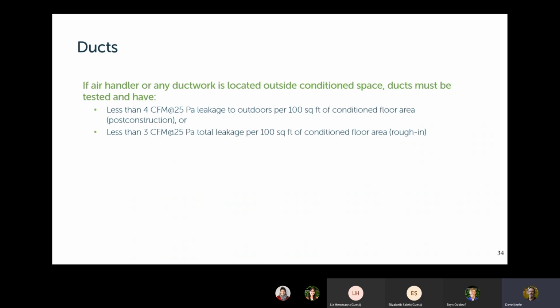So the code recognizes this, and what it says is if you choose to run through the attic or some other unconditioned space, first of all, you have to very, very heavily insulate all the ductwork. And you have to have the ductwork tested. This is a test similar to a blower door test. It uses equipment that's the same in concept, a little different in terms of the size of the fan and the way that it hooks up, but it's the same type of test. And then you have to pass that test. Presumably you have to pay for somebody to conduct that test. So the code makes you jump through a couple of pretty big hoops if you choose to send any ductwork outside. So please don't send any ductwork outside.